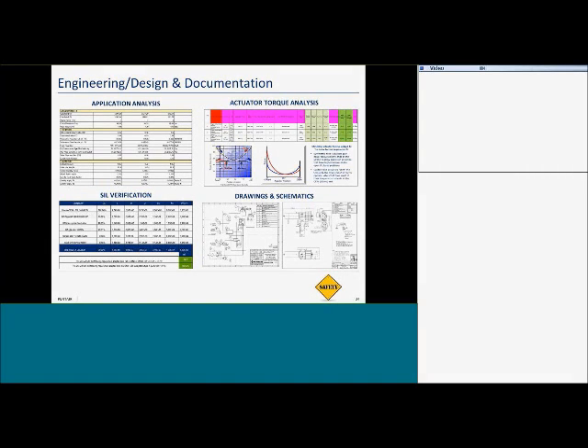SIL verification for the automated valve package is extremely important. We are building up a program within Pentair where we have people that can do this SIL verification module in the bottom left-hand corner. Really, what we're doing here is we're taking all of the PFD numbers from all the certificates for each of the components in the automated valve package, and we're making sure that the combination of all of these components provides the proper SIL level so that we know that we're compliant for our customer. And then again, customers need drawings, and schematics are critical for these types of packages. So really, this is some of the most highly engineered and complex automated valve packages that we're seeing in our industry.